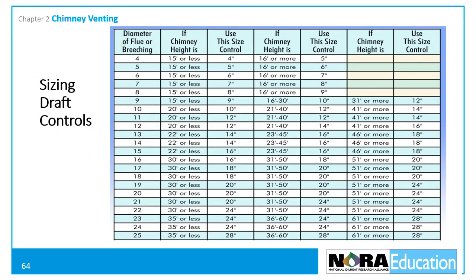For most applications, appliance manufacturers recommend that the draft control should be the same size as the flue pipe. Tall chimneys often require larger controls to prevent overdrafting. For example, an appliance with a 6-inch flue pipe typically requires a 6-inch control if the chimney is 15 feet high or less; however, a 7-inch control is recommended if the chimney is 16 feet or higher. During high draft conditions, a smaller control may not be able to completely manage the excessive draft load.